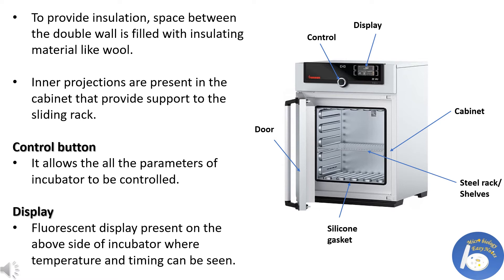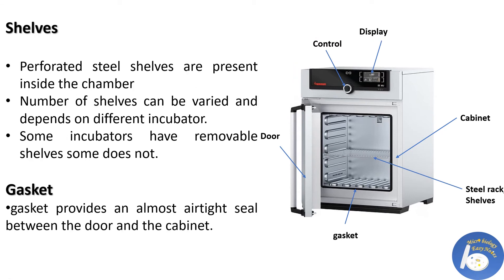To provide insulation, the space between the double walls is filled with insulating material like wool. Inner projections are present in the cabinet that provide support to the sliding racks or shelves. The control button allows all the parameters of the incubator to be controlled. The fluorescent display is present on the top or side of the incubator where temperature and timing can be monitored. Perforated steel shelves are present inside the chamber where the material is kept; the perforations allow movement of hot air throughout the inside. The number of shelves can vary depending on the incubator — some have removable shelves and some do not.